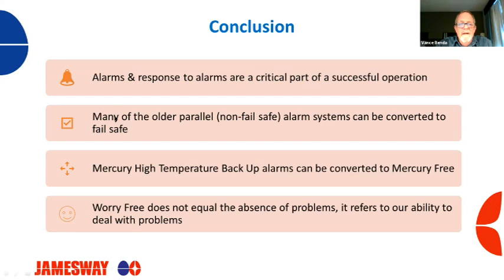A little bit of good news is many, if not all, of the older parallel non-fail-safe alarm systems can be converted to fail-safe. If you're interested in doing that, contact your salesman or Dr. Bramwell or anybody, and let's get a technician out to evaluate your wiring and see what all we're going to have to do. But we can most often convert your old systems, as well as your mercury high temp backup alarms can be converted to mercury free. But as I said earlier, just be aware that when you do it, you're going to have to replace your mercury thermostats, and you're going to have to replace that old 3-conductor wire with 5-conductor.